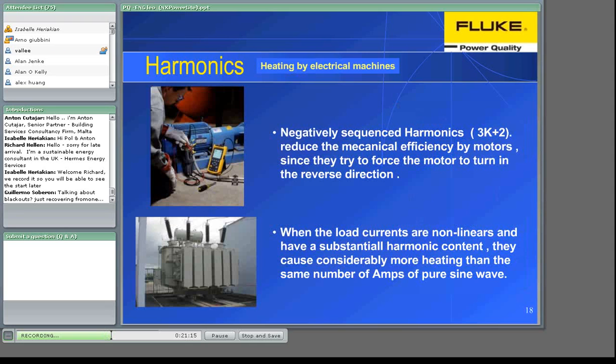Influences of harmonics on electrical machines, motors. Voltage harmonics cause, as we said, extra losses in direct line connected induction motors. The fifth harmonic creates a counter-rotating field, whereas the seventh harmonic creates a rotating field beyond the motor's synchronous speed. The resulting torque pulsing can cause problems on couplings and bearings. Since the speed is fixed, the energy contained in these harmonics is dissipated as extra heat, resulting in premature aging. Harmonic currents are induced into the rotor, causing additional heating also, reducing, by the way, the efficiency even further.